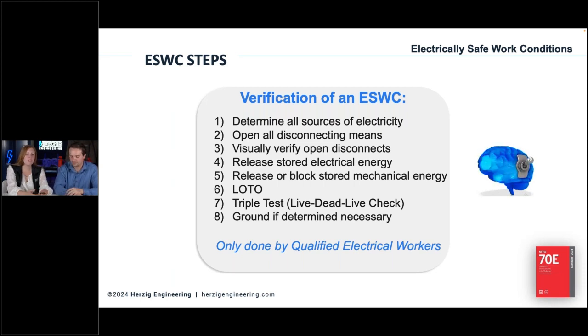Right. So the additional step, a lot of times it's lock it out, tag it out, and then try to turn it back on. That's not good enough, because there are times where there could still be energized parts, but the machine or equipment won't quote unquote turn on or operate because you have a spot welded shut leg, or something happened, there was a fault, and so the equipment doesn't run, but it is still energized. So LOTO and trying to turn it back on is not good enough whenever it comes to electrical safety. You actually have to get the meter out, check on a known source that your meter works, go to the point of work. This is kind of a change in the 70E if you didn't know. It's not just the secondary side of the disconnect. You have to go where that person is going to be sticking their hands. That's where you verify 0 voltage, and then go check a known source again. Okay. And then grounding is more common if you have medium voltage, high voltage systems, but there are some other scenarios where you might need that.